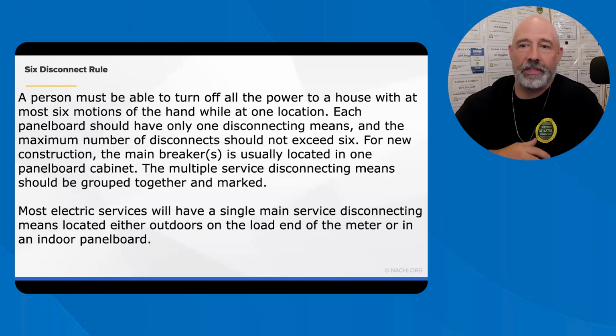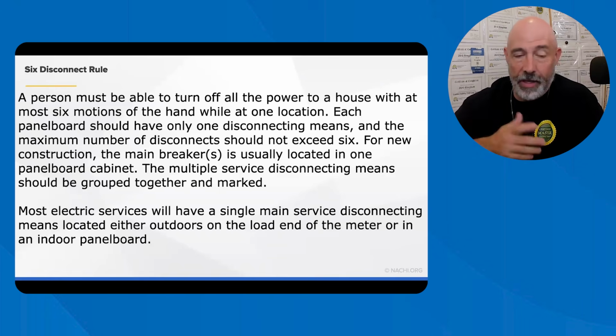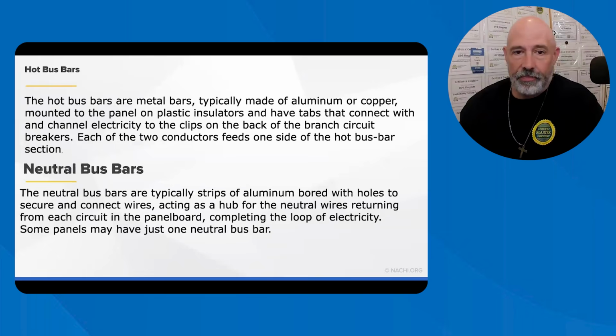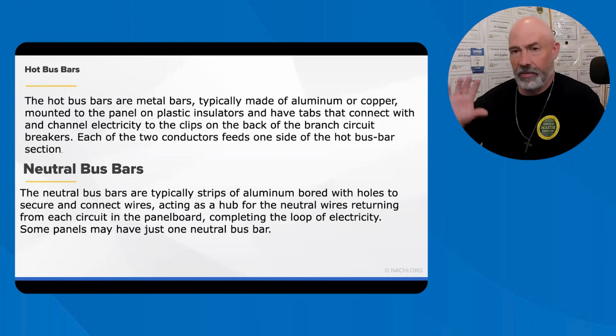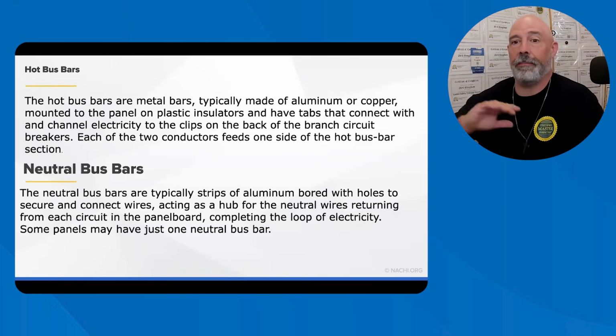Multiple service disconnect means should be grouped together and marked properly. Most electrical services have a single main service disconnecting means located either outdoors on the meter or in an indoor panel board. So lately, I called that out on a couple of new constructions, and the jurisdiction actually said, no, we didn't do that here. So just FYI, jurisdiction overrides anything the NEC says. NEC is not law, it is code. And code means that it can be interpreted and it can be adopted and it might not be adopted.